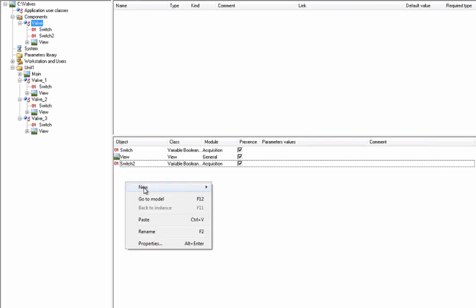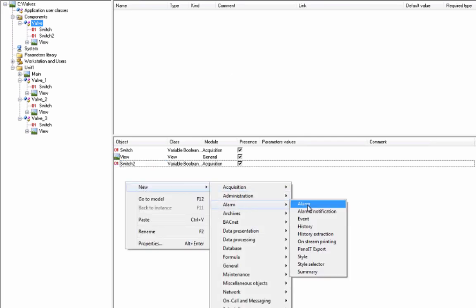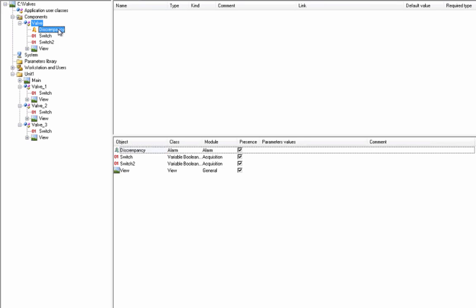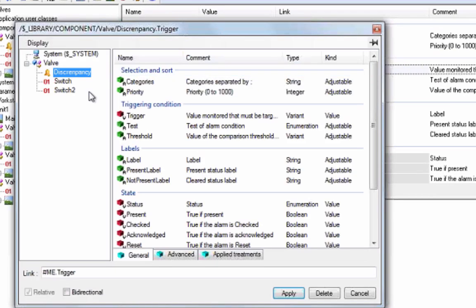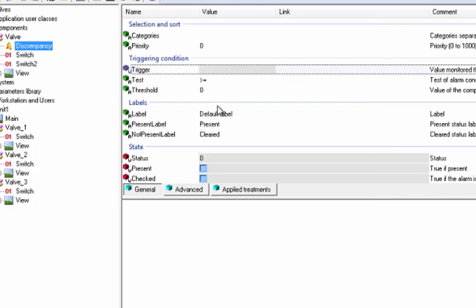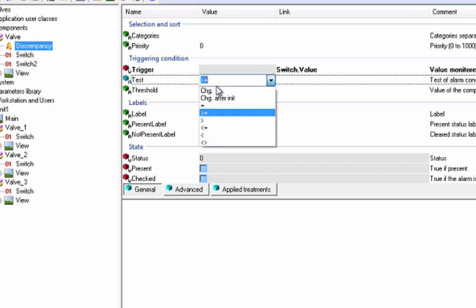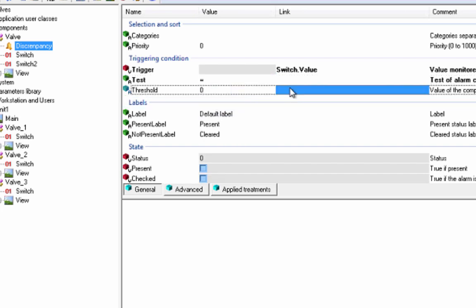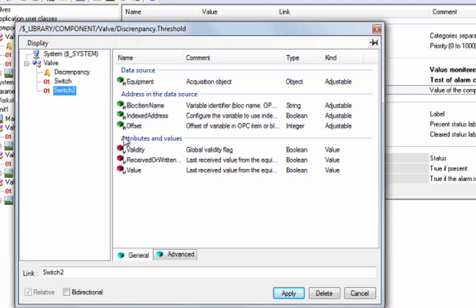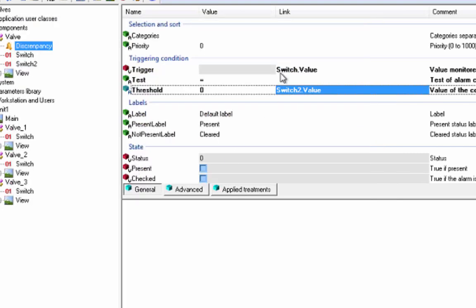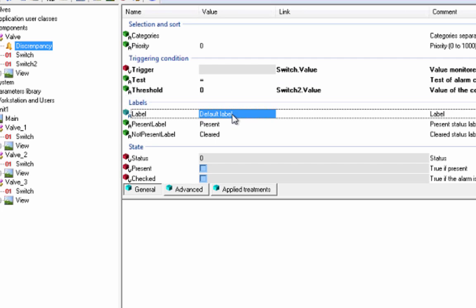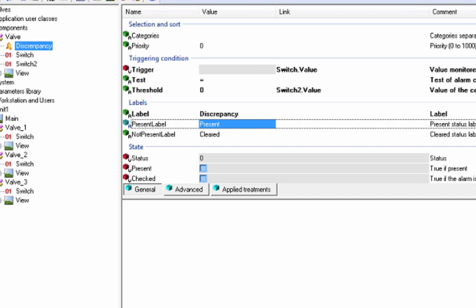And with these 2 switches, I can create an alarm that will tell me that I have a discrepancy between these 2 inputs. For instance, when the 2 switches are equal, it means my valve is blocked in an awkward position. So I define my alarm's present condition to be switch value equal switch 2 value. And this alarm needs to have a label, at least discrepancy.